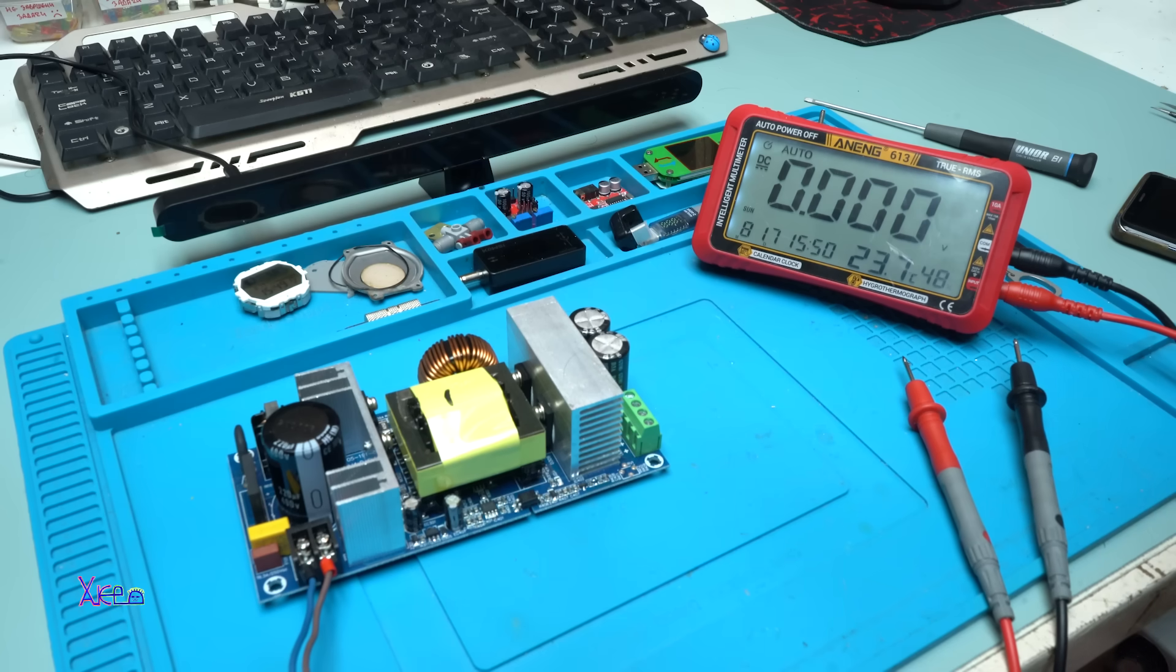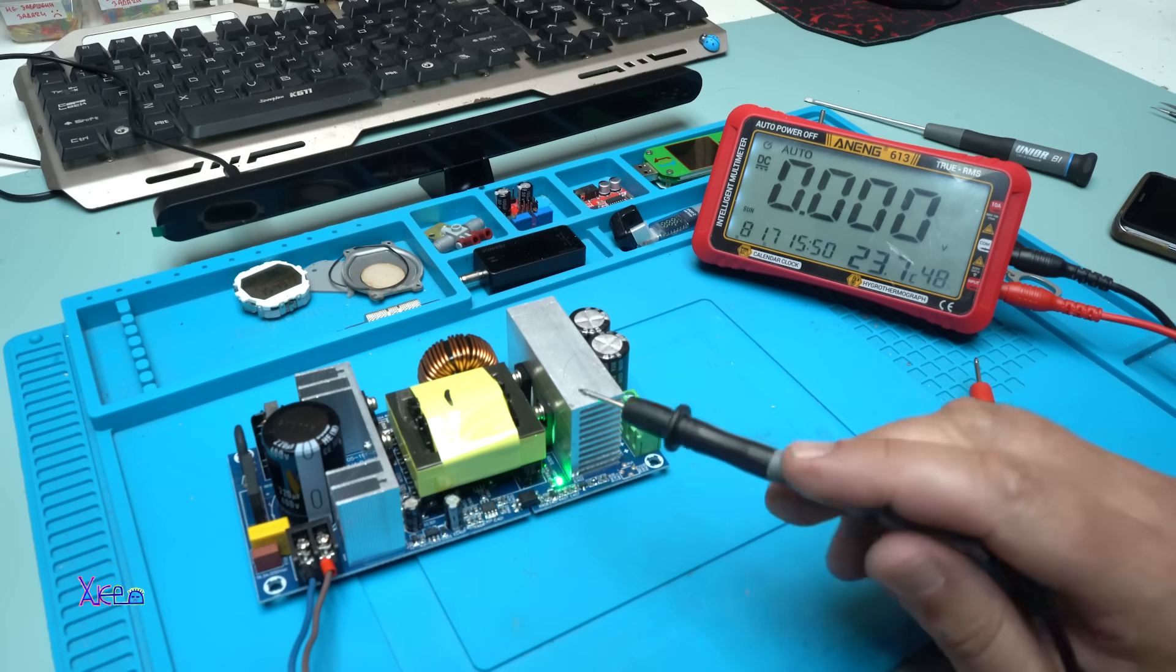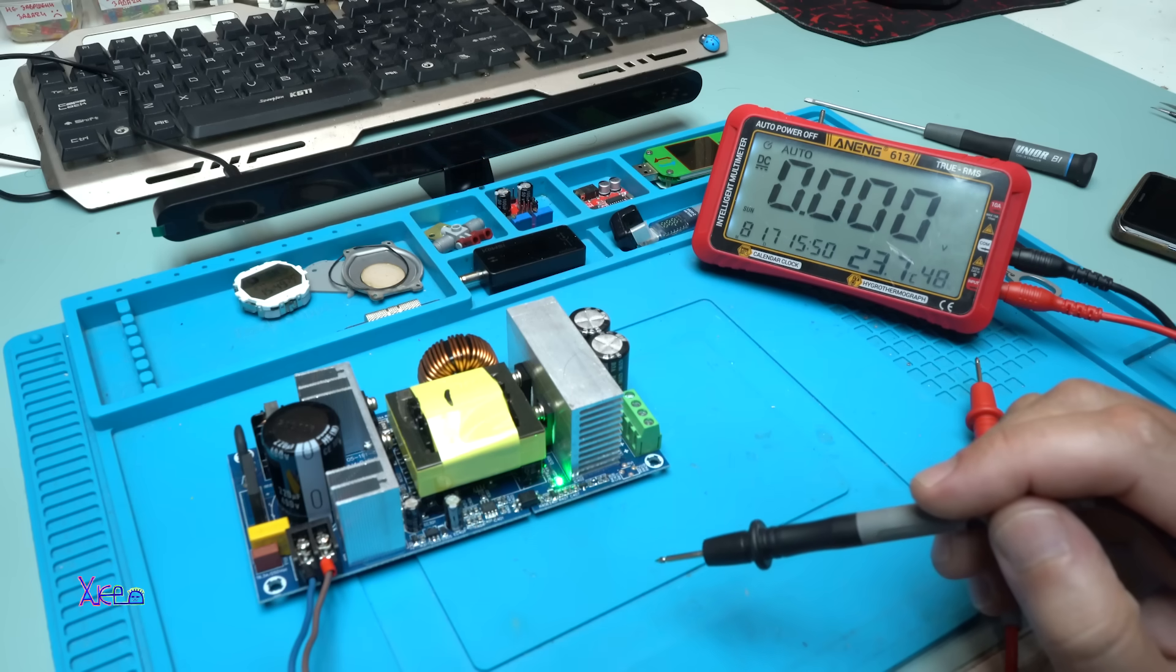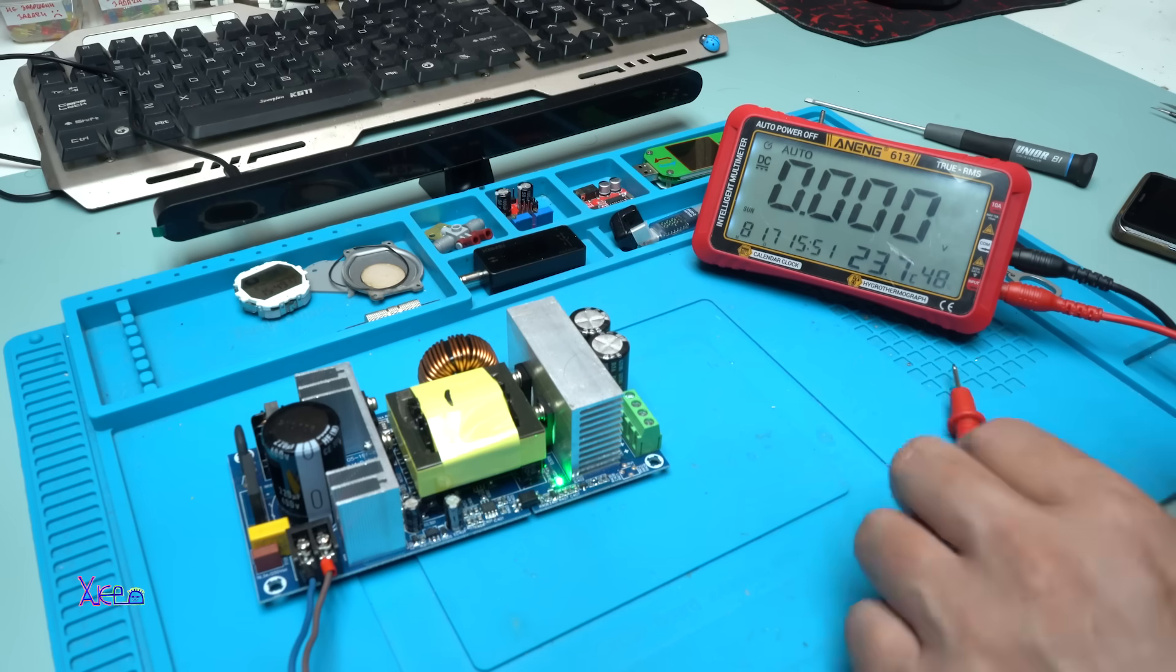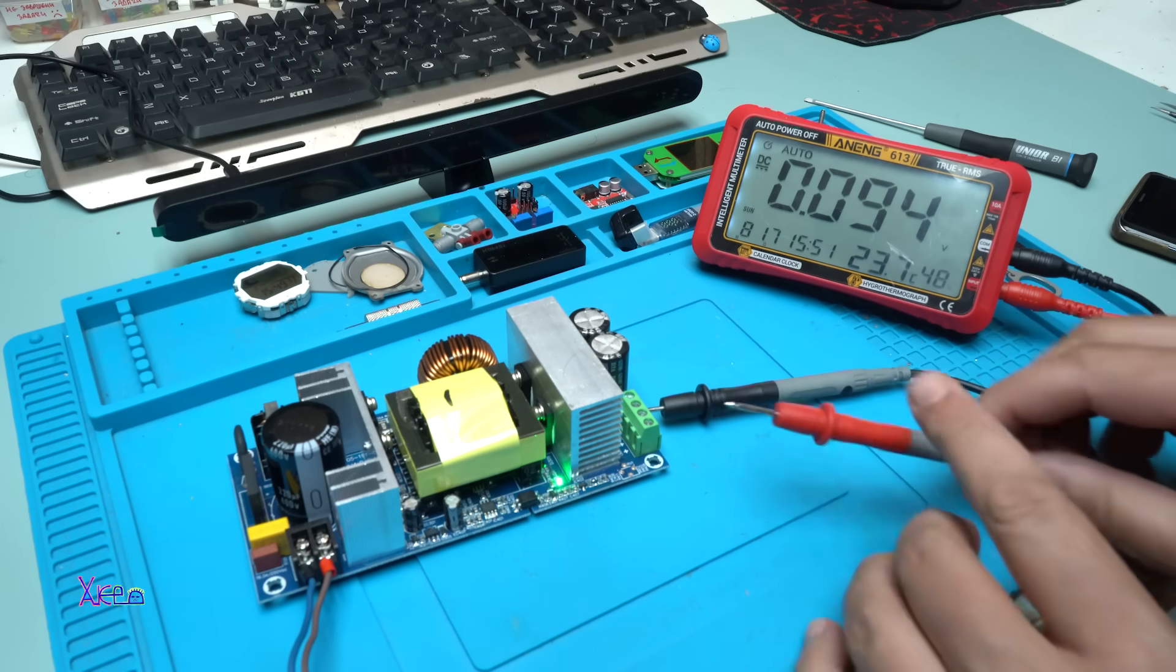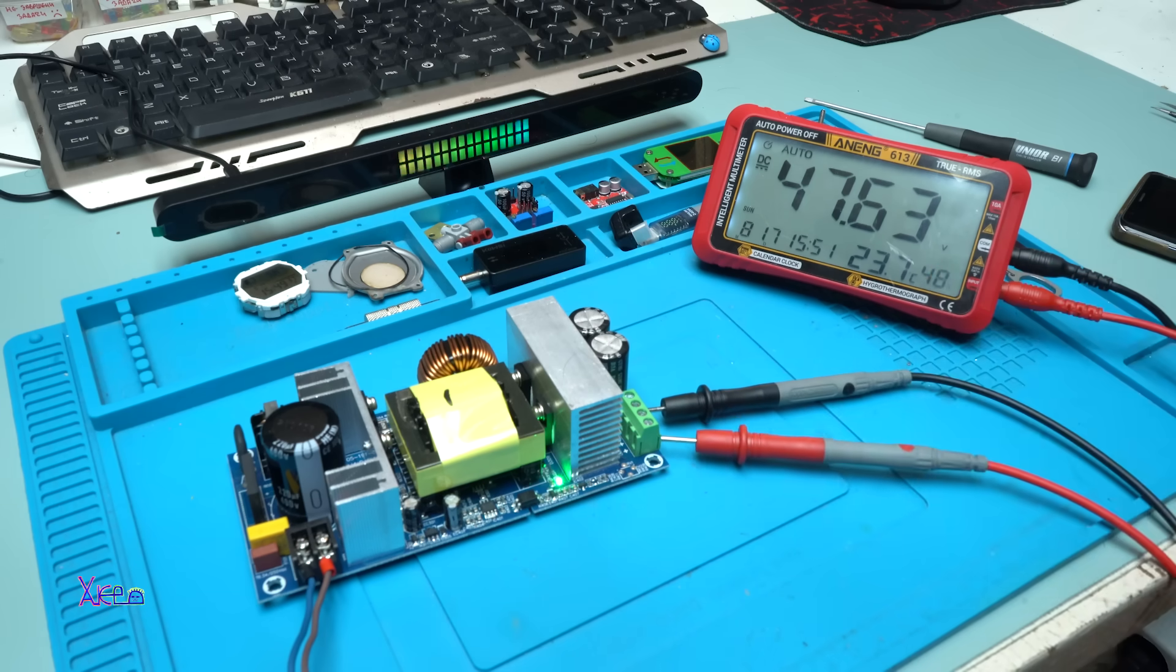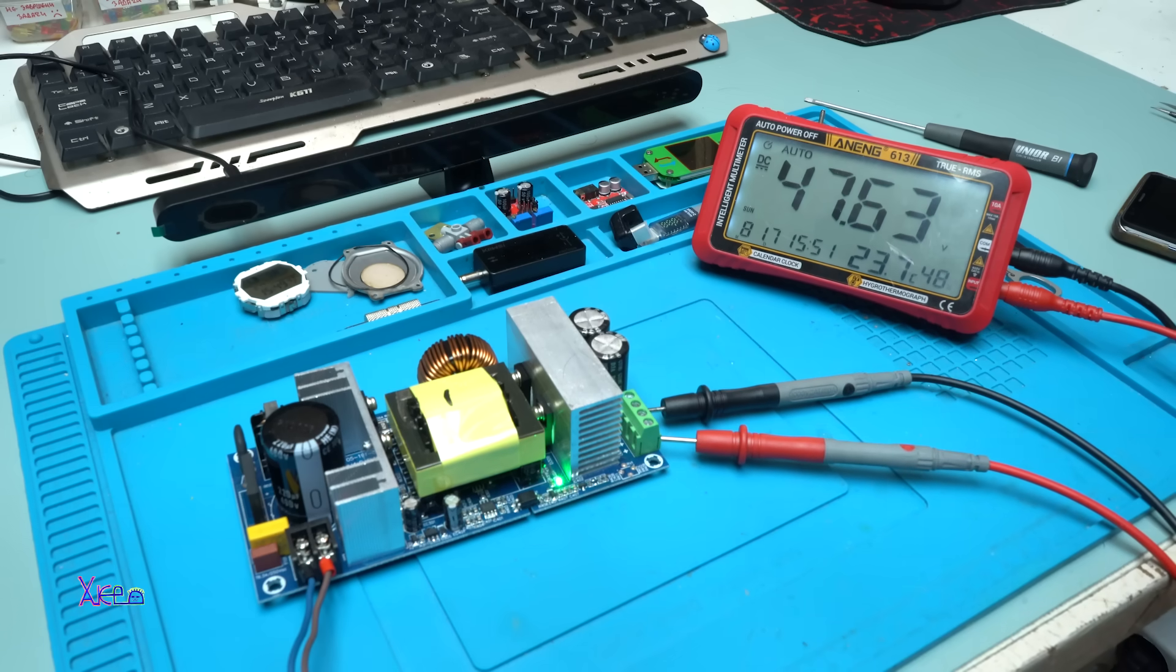And yes, right here we have a green light, meaning that this power supply module of 48 volts and giving 6 amperes is working fine. Let's measure the output voltage right here, and what it says on the multimeter - 47.6 volts. Beautiful.